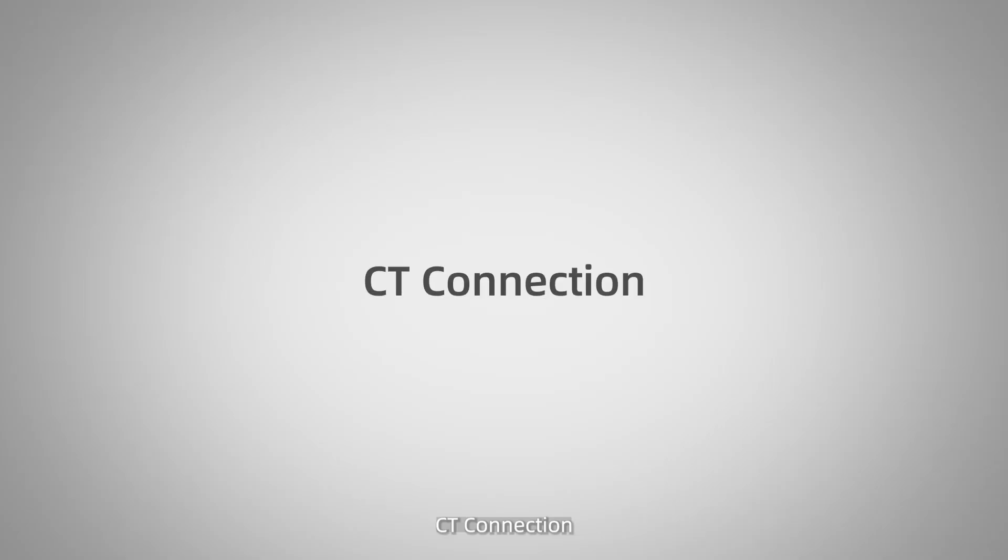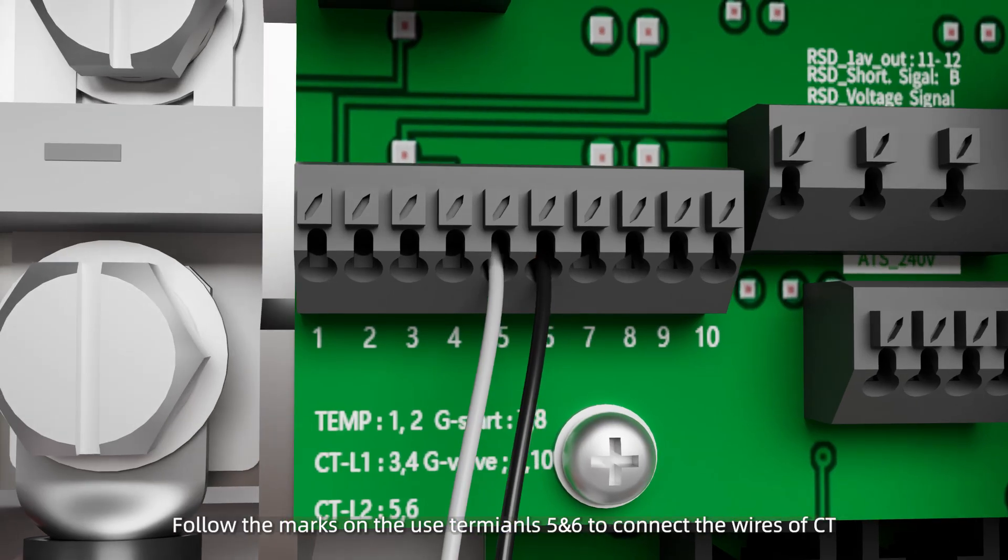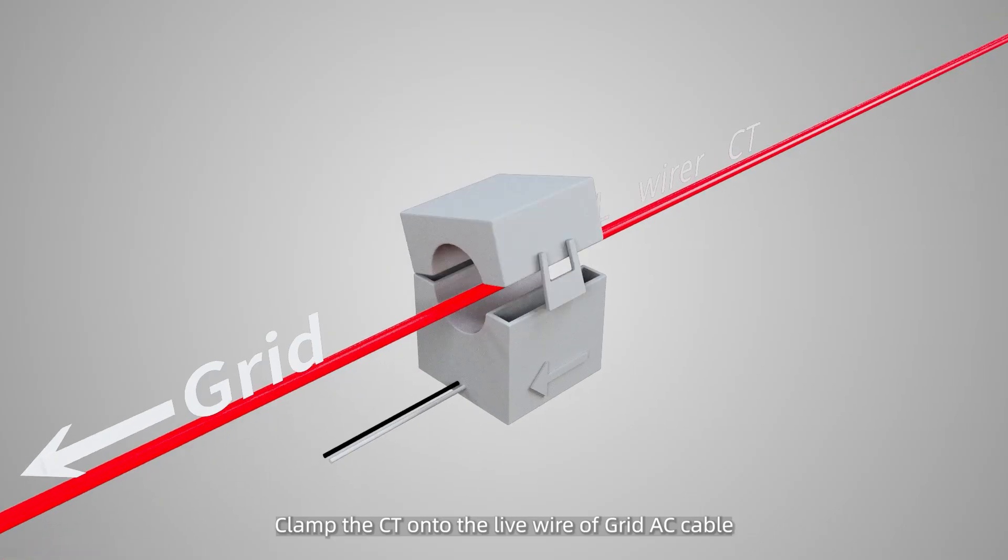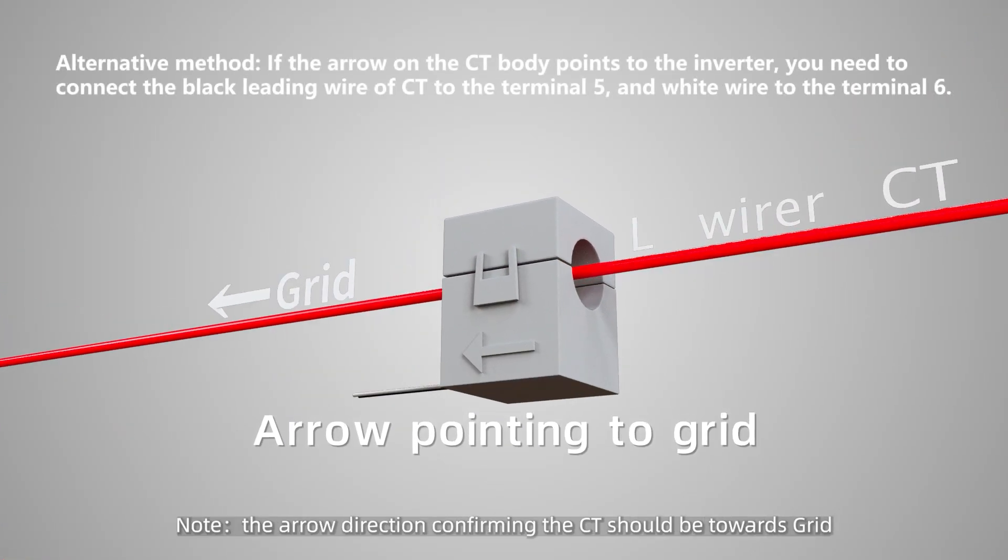CT connection. Follow the marks on the use terminals 5 and 6 to connect the wires of CT. Clamp the CT onto the live wire of grid AC cable. Note, the arrow direction confirming the CT should be towards grid.